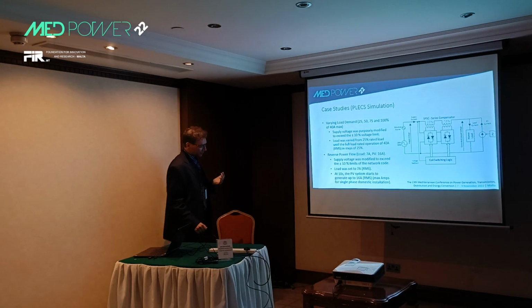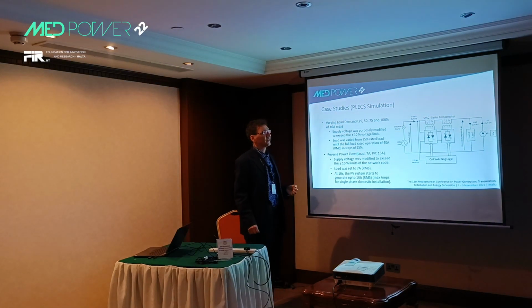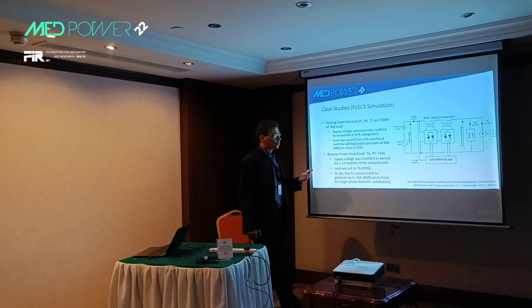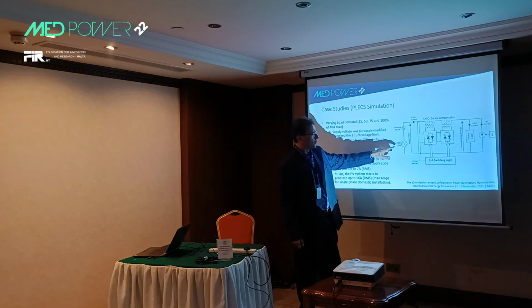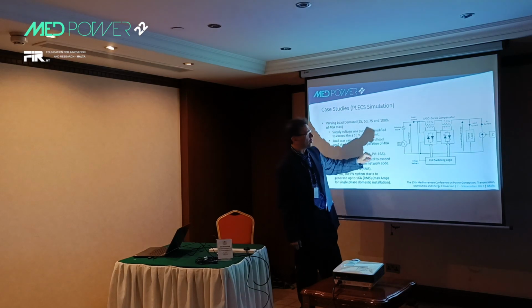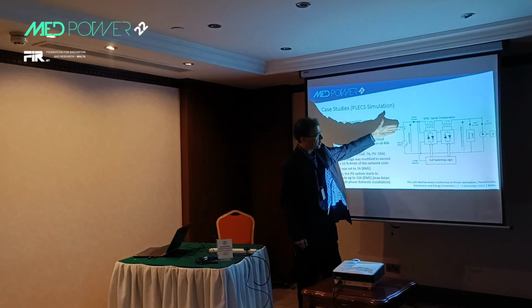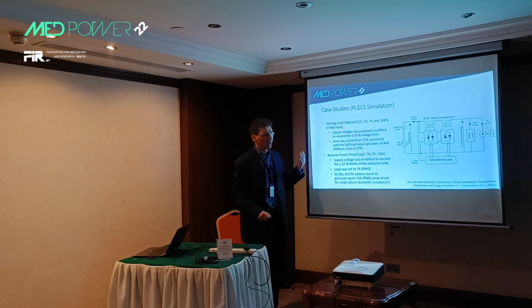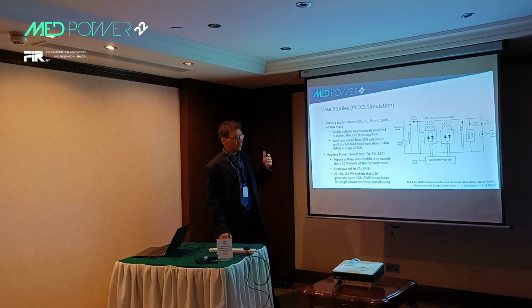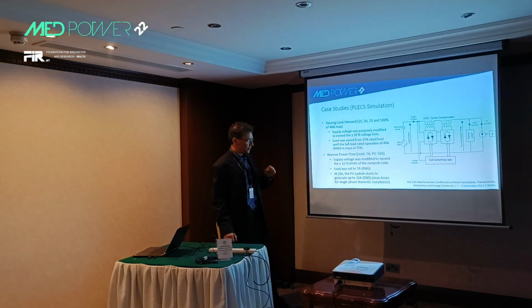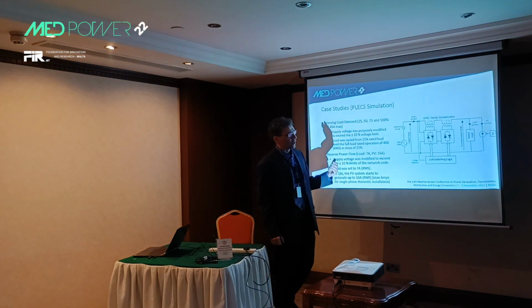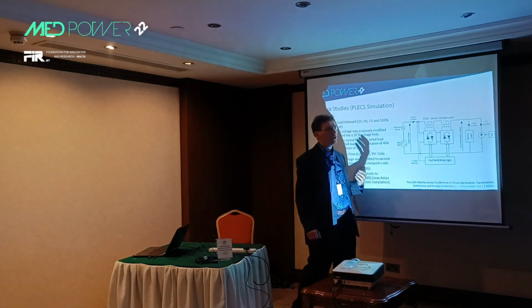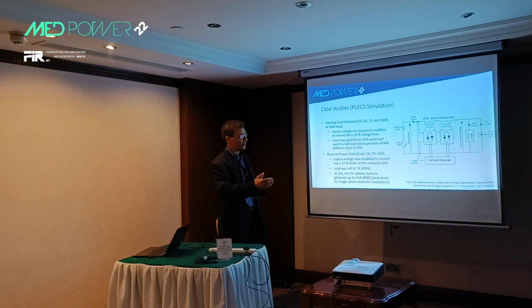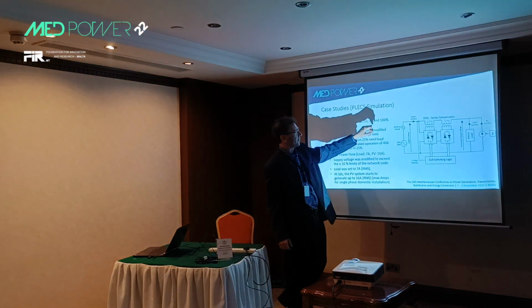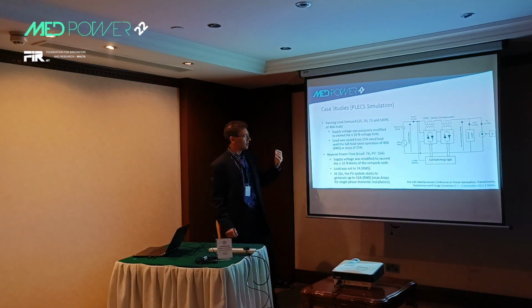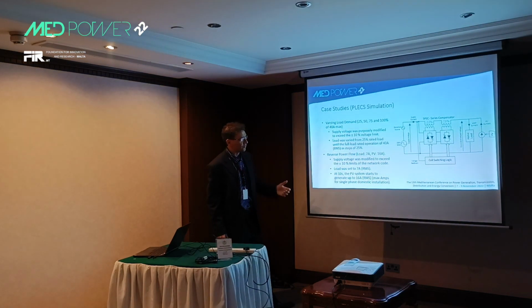So the first step was for us to simulate our concept. What we did is we had our standard 230 volts 50 Hertz, and we put a distortion source additional to that to get a negative effect of the voltage going above and below the EN 50160 standards. Then, usually when we have got equipment under test, you need to test it using all the rated current conditions. In this case, we did 25, 50, 75, and 100% of rated load. In this case, 40 amps maximum for a Maltese household.